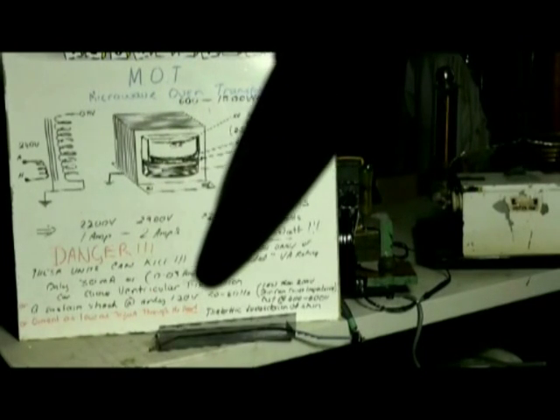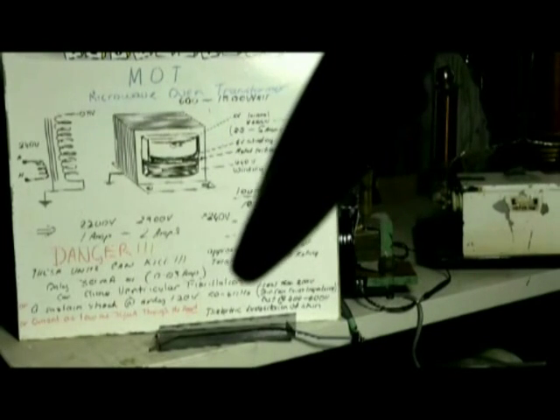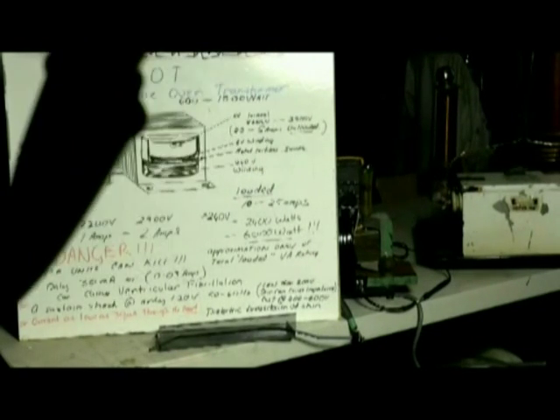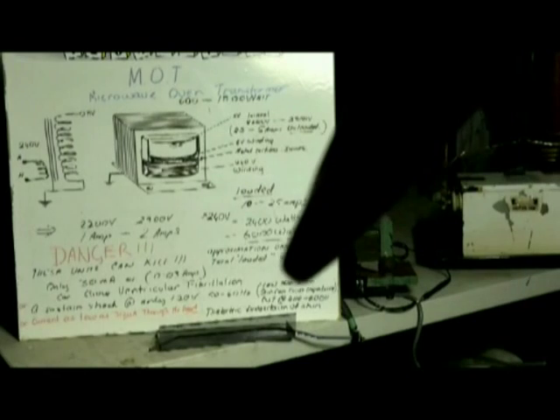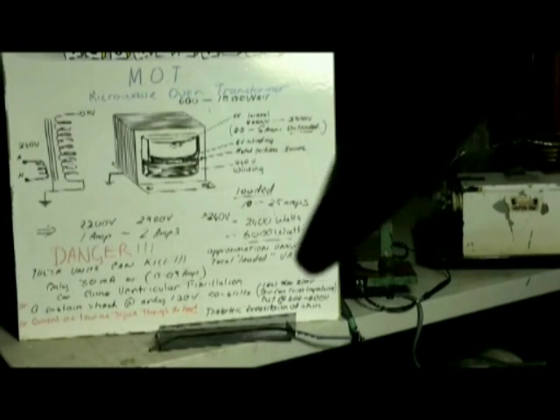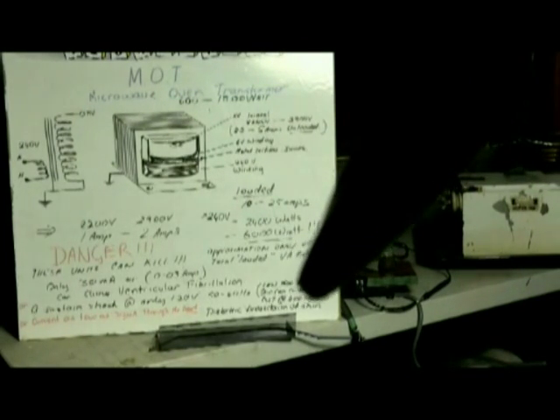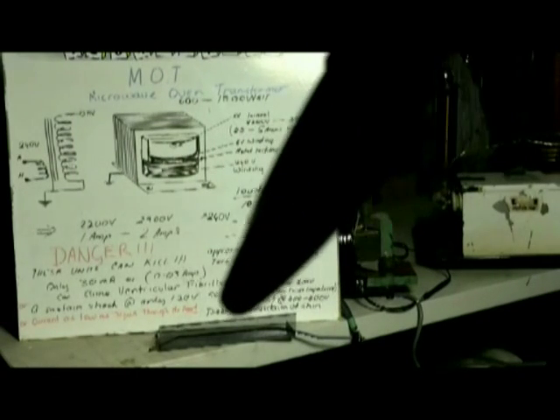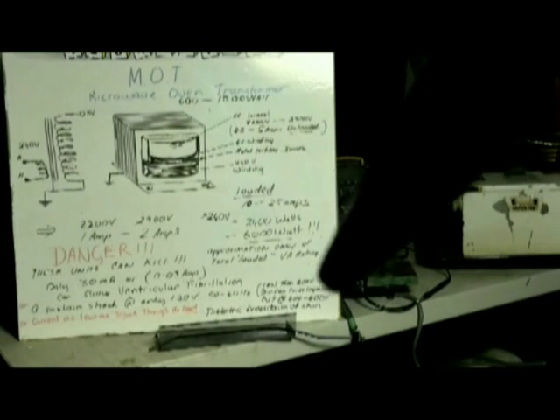Only 30 milliamps, which is 0.03 amps, can cause ventricular fibrillation. A sustained shock of only 120 volts at 50 to 60 hertz can do the same, or a current as low as 30 microamps passing directly through the heart. Less than 200 volts, the skin can cause impedance which could protect you, but at 400 to 600 volts, there's a dielectric breakdown of the skin and you've got very little protection.